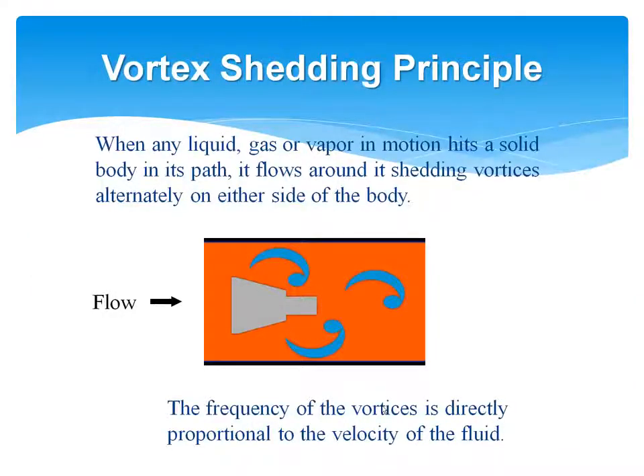Bottom line here is, in a vortex style meter, the frequency of the vortices coming off of the obstruction is directly proportional to the velocity of the fluid. And so what that drives to is a meter that is fairly robust. There are no moving parts, and so you get a fairly constant calibration over a long period of time. You do have to watch out, as we mentioned in some of our earlier examples, on sizing, and make sure you've appropriately selected the correct size of the meter. But again, it's something that's been used quite a bit in steam flow measurement.